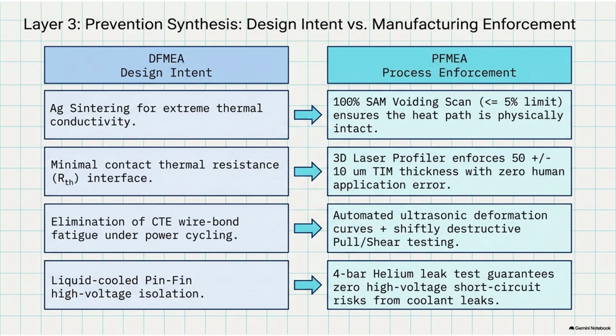Because a massive block of copper takes a lot longer to heat up than a microscopic sliver of silicon. Precisely. So the microcontroller takes the slow baseline temperature reading from the NTC physical sensor, then looks at the real-time electrical data. It knows exactly how many amps of phase current are being pushed to the motor at this exact millisecond, the DC bus voltage, and the exact switching frequency of the transistors.